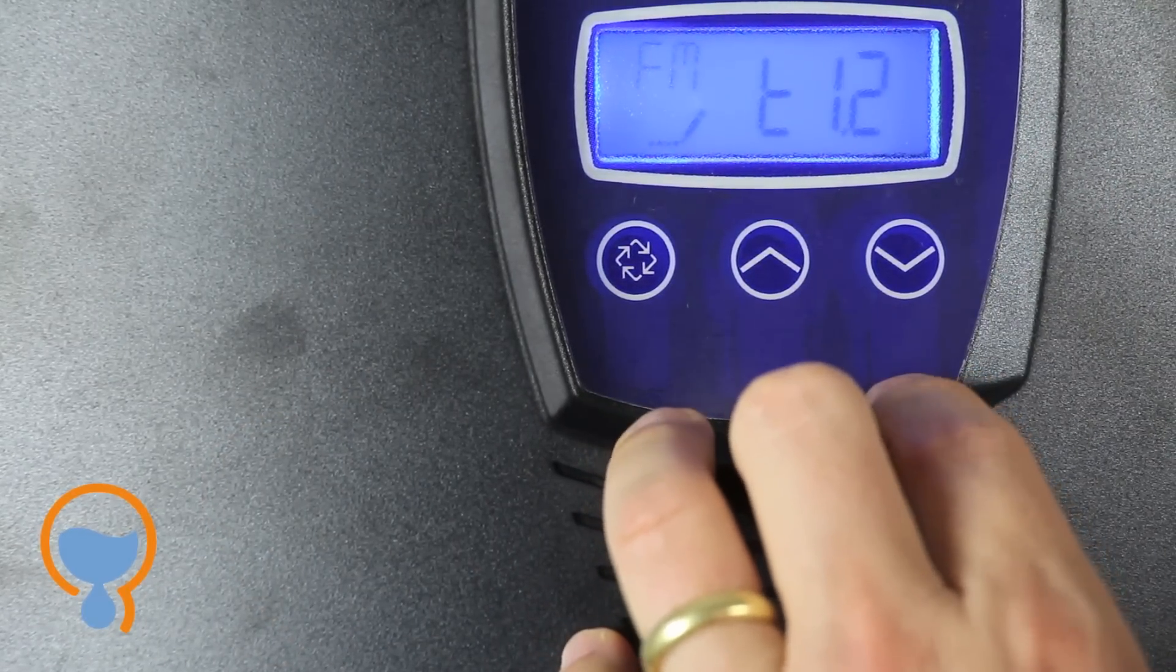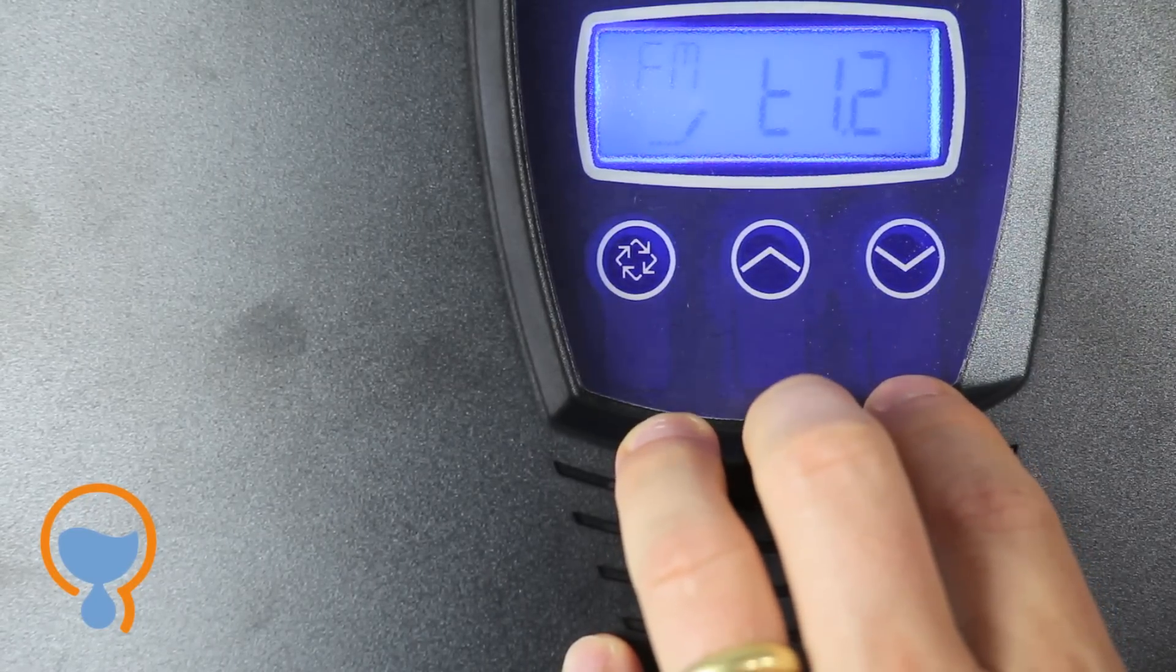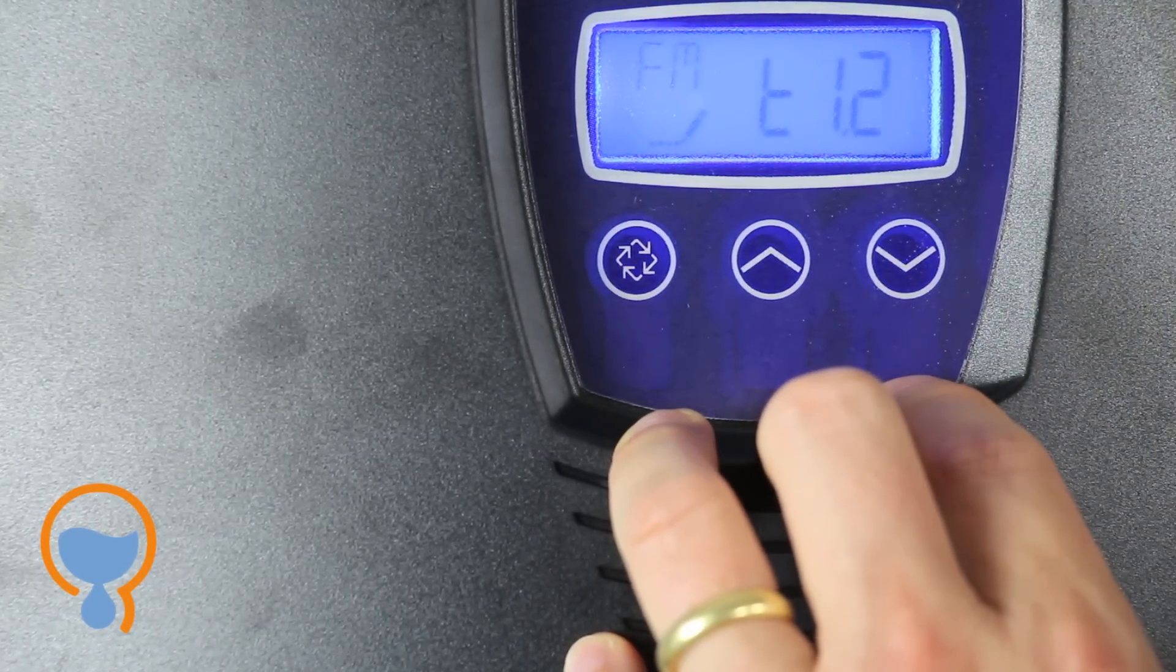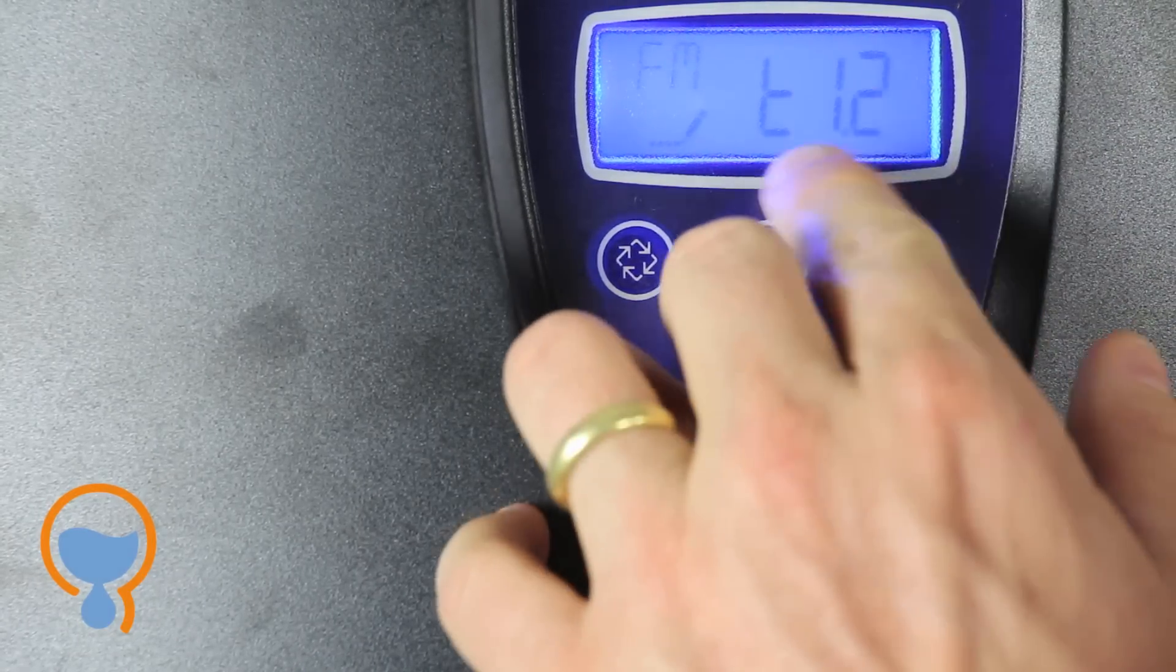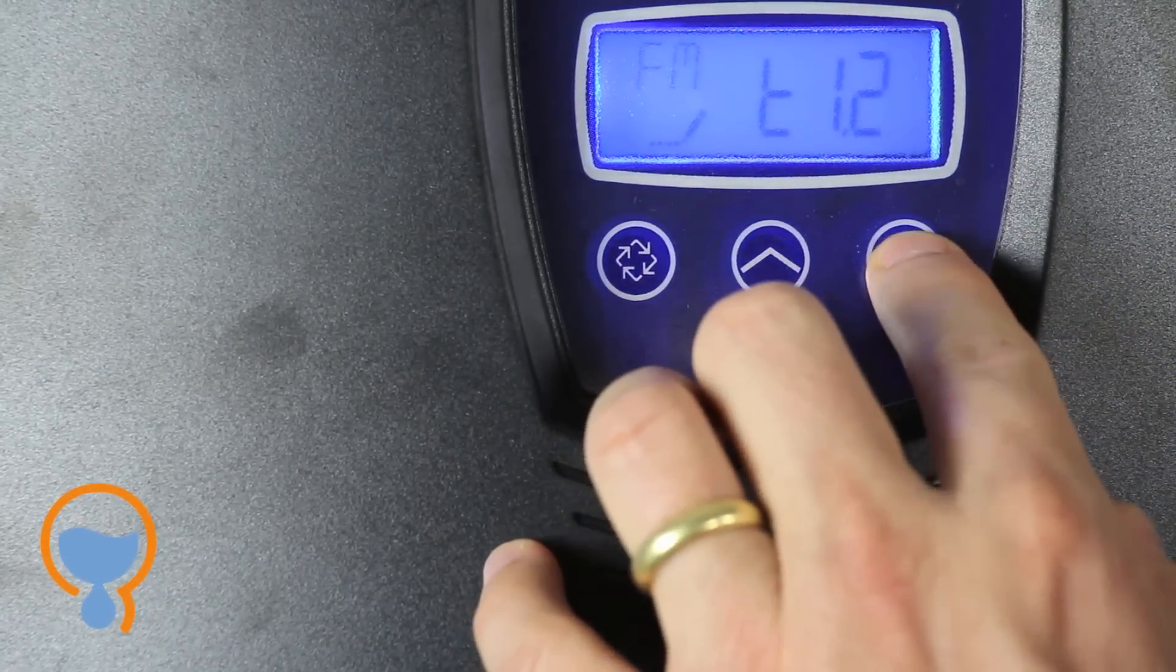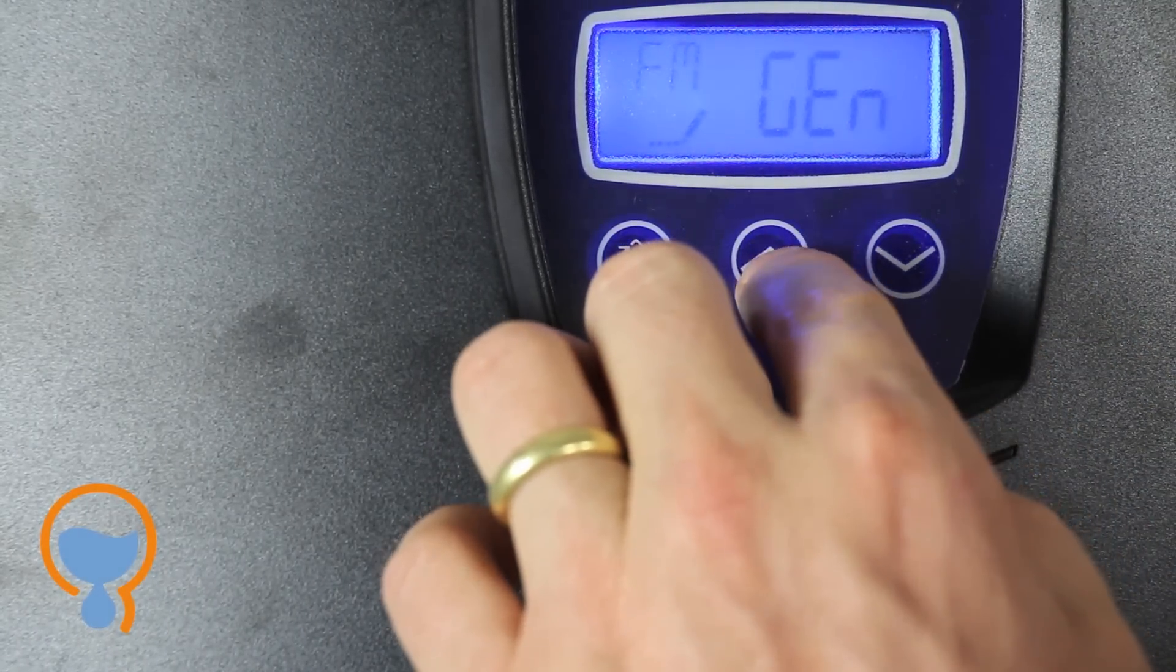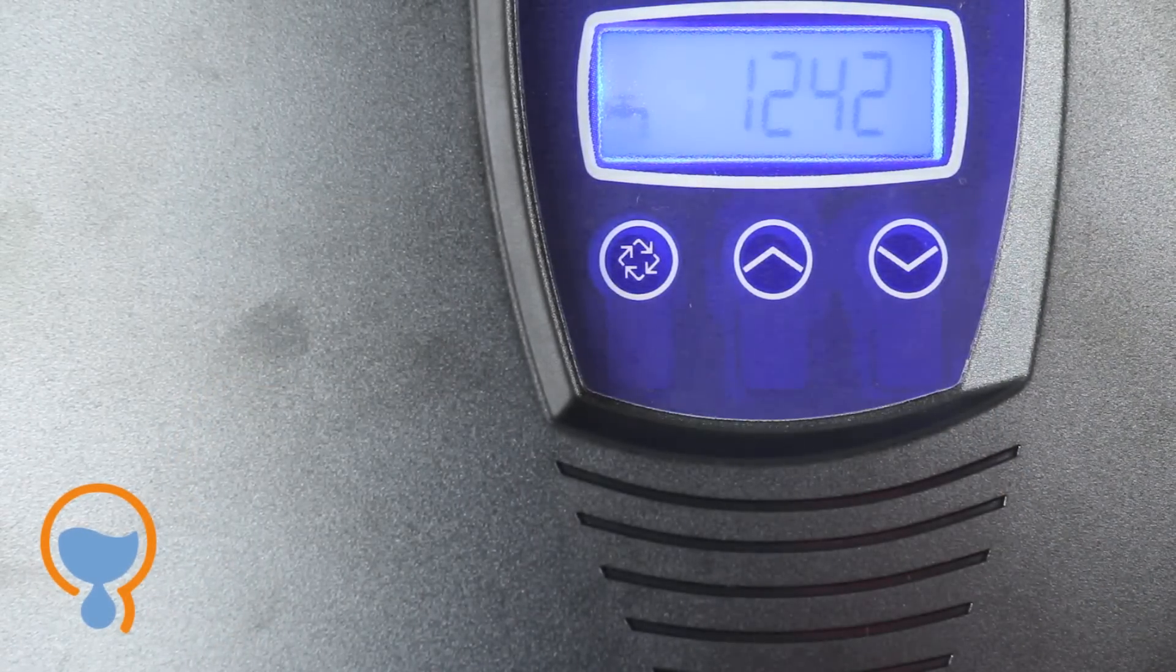Lastly, FM refers to the meter type. That's the meter or the turbine that's measuring the water flow. And that is back on the rear side of the control valve. In this case we want it to say T1.2. Yes, believe it or not, that's a lowercase t. A number of different options, but we want the T1.2. We press enter. And that'll do it.